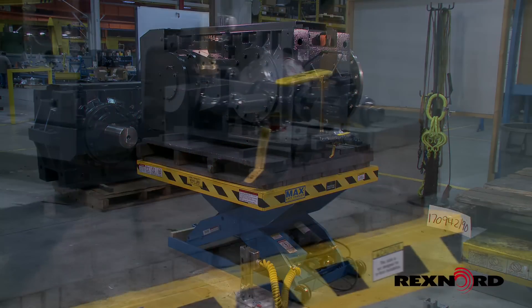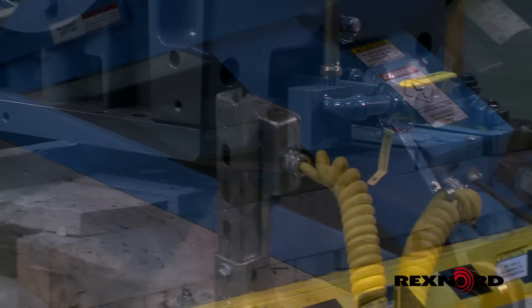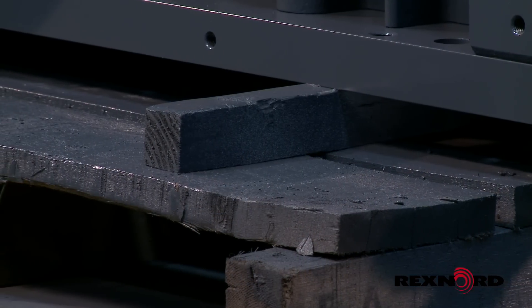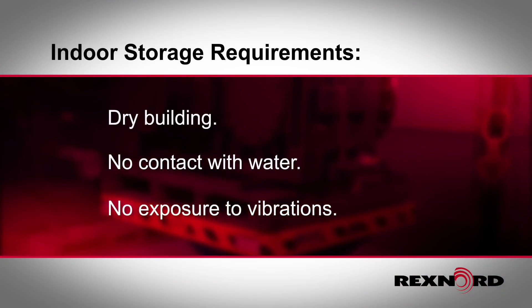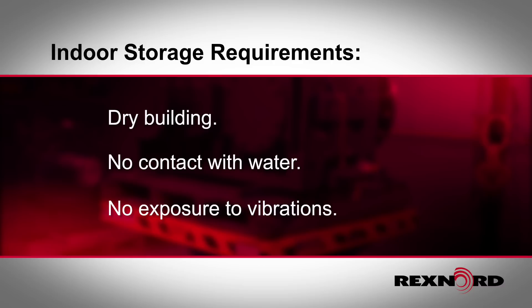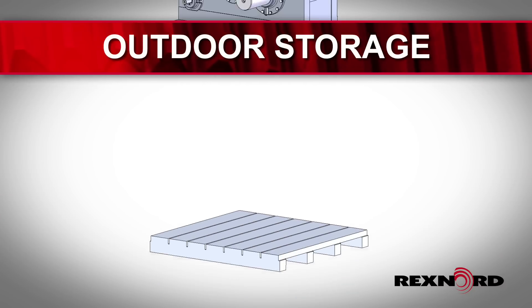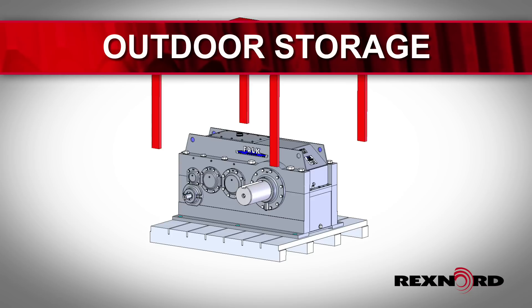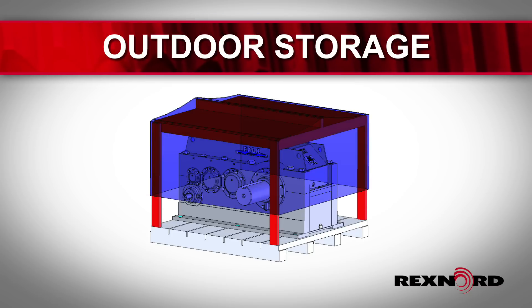It's important to keep the unit in an isolated spot when placing it into storage. The best place is a dry building where the drive will not come in contact with water. Keep the gearbox away from any form of vibrating machinery and away from the driving path of forklifts or similar equipment that could transmit vibrations to the stored unit. An outdoor shelter can also be used for storage. The gearbox should be positioned on blocks, keeping it off the ground. Have a sturdy frame around the unit and cover it with a tarpaulin, leaving the bottom open for ventilation.